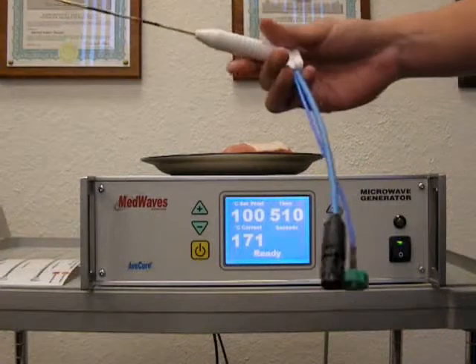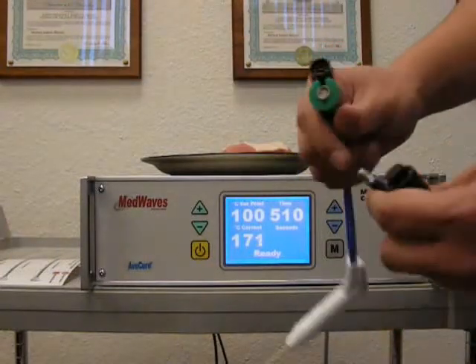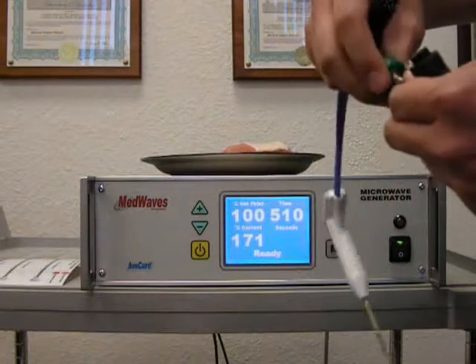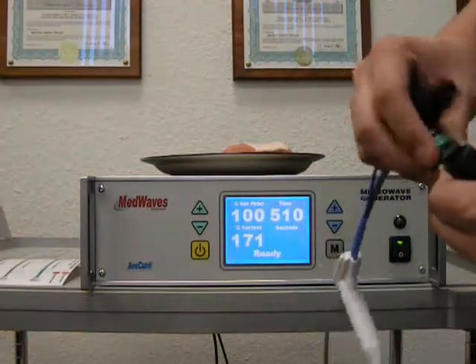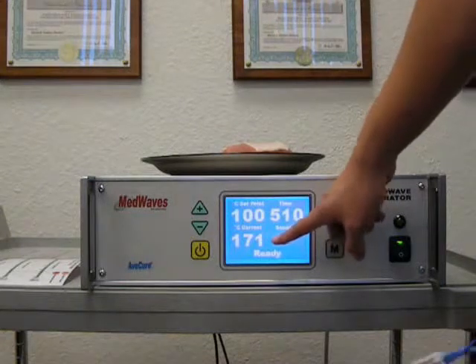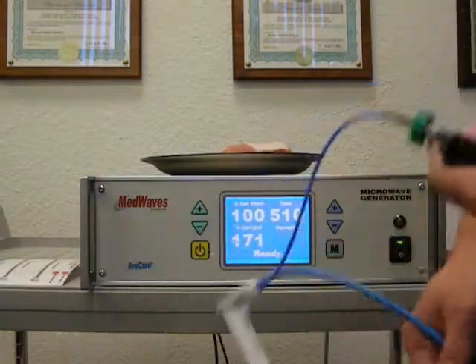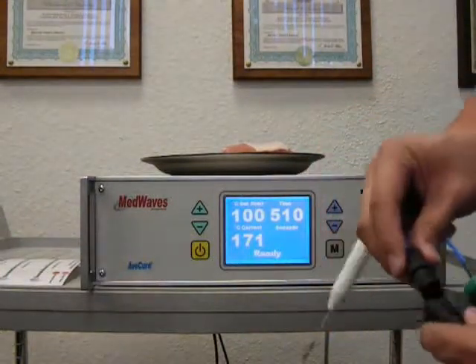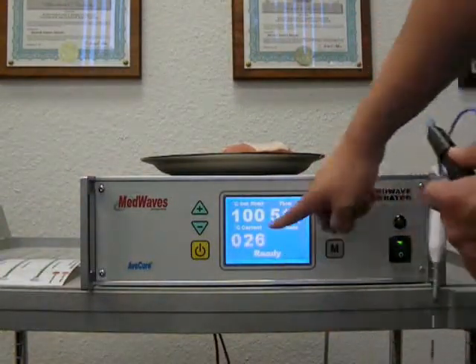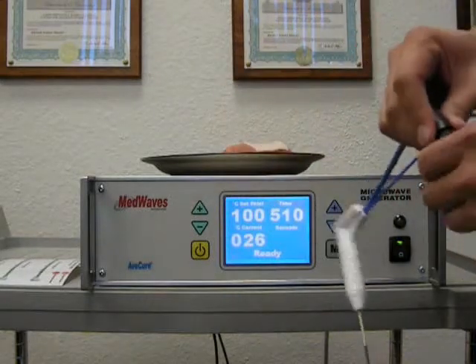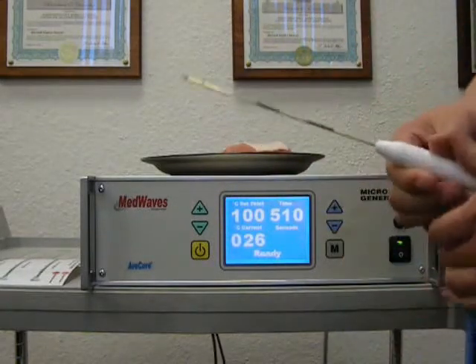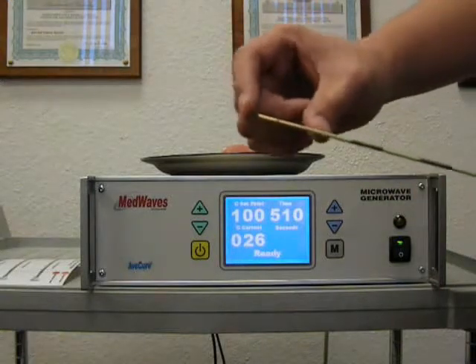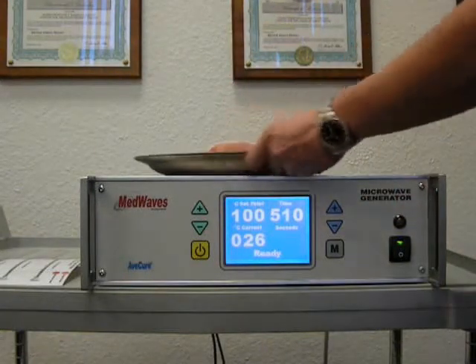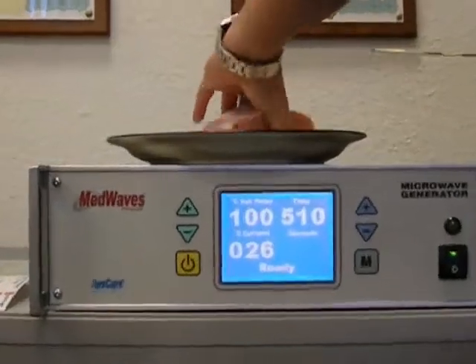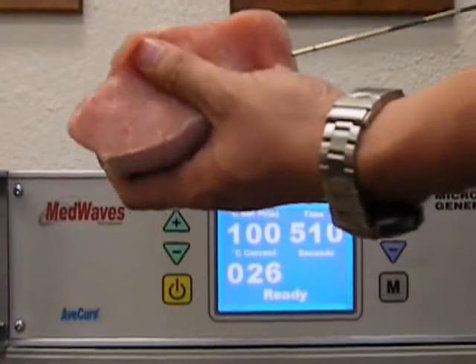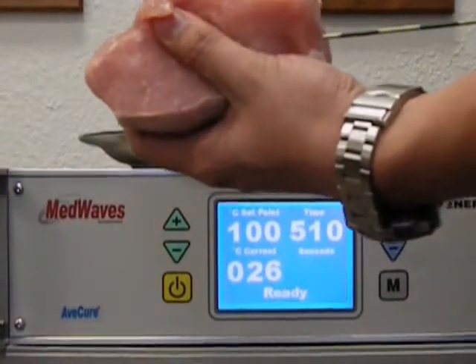So here I have the 14-gauge probe, 15 centimeter shaft. And I'm connecting the extension cables. As you can see, the temperature is reading a very high value right now, which signifies the temperature cable being disconnected. Once I connect it, the temperature will start reading from the probe. With the 14-gauge probe, it has a 4 centimeter active antenna. When inserting into the tissue, you want to make sure that the entire antenna goes into the tissue.